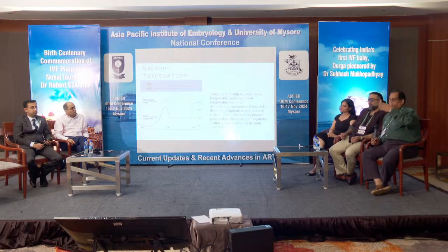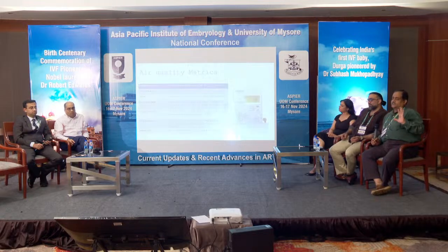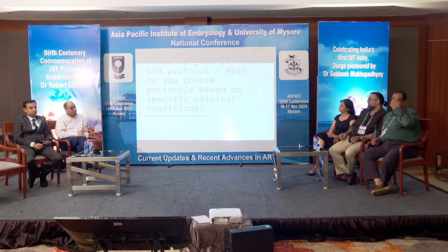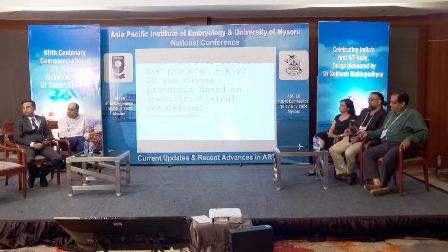Whichever suits most of the laboratory working people. So averaging it out, around 24, 25 is the ideal ambient temperature for the consistent performance of your incubator as well as the people working in the environment. So now I just hand over to sir.